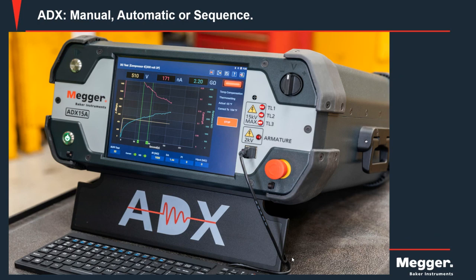Now, we also have manual mode. Now, what manual mode means is that we can just connect the leads straight up to a motor, push the button and turn the voltage up, and we can start doing an insulation resistance test instantly. We don't have to pre-program it.